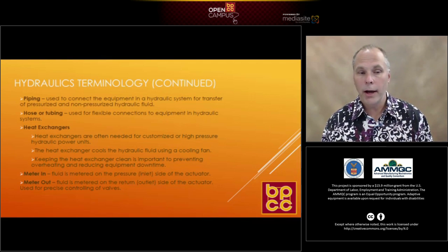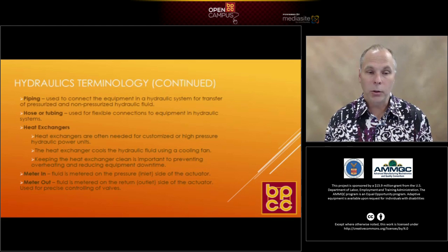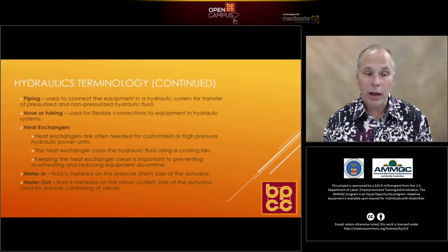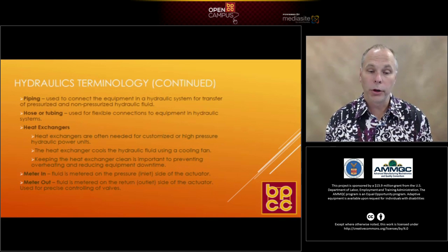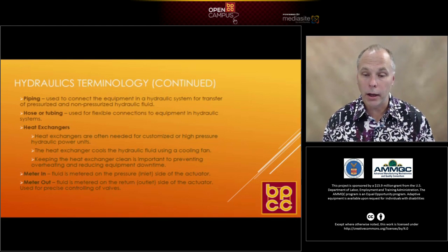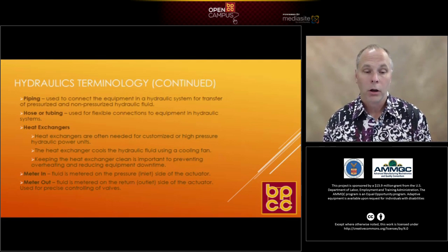When you pressurize liquid, you're compressing the fluid, and as you compress it you usually create heat. So sometimes you have to have heat exchangers. Sometimes you're pushing fluid through a system and it's creating friction, and that friction creates heat. Heat exchangers are often needed in customized or very high-pressure hydraulic power units. The heat exchanger cools the hydraulic fluid using a cooling fan, which can be electric, hydraulic, or pneumatic.